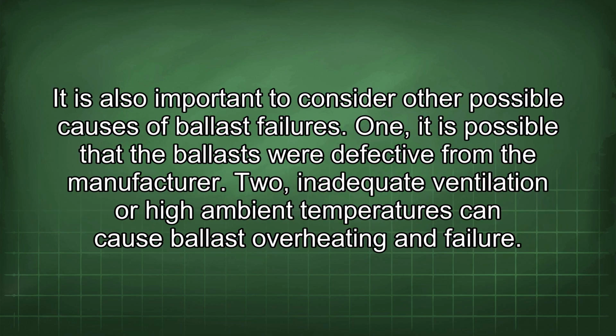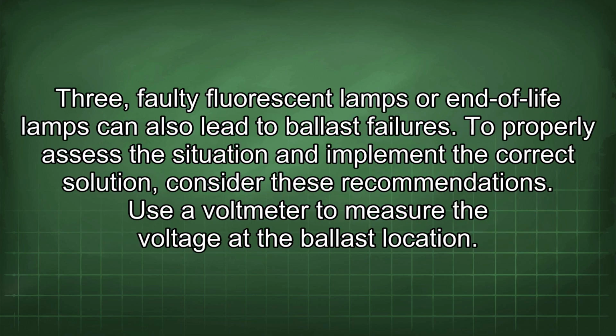It is also important to consider other possible causes of ballast failures. 1. It is possible that the ballasts were defective from the manufacturer. 2. Inadequate ventilation or high ambient temperatures can cause ballast overheating and failure. 3. Faulty fluorescent lamps or end-of-life lamps can also lead to ballast failures.